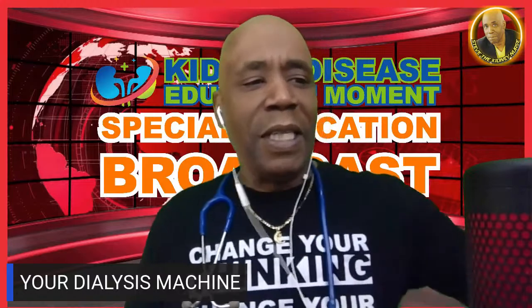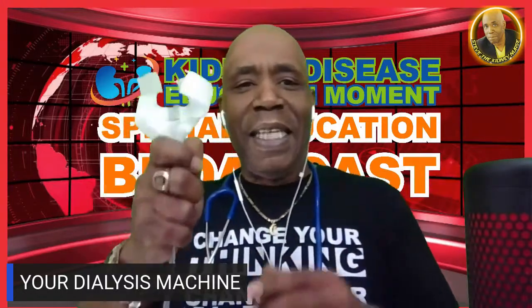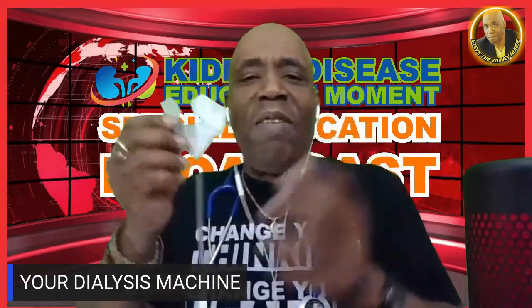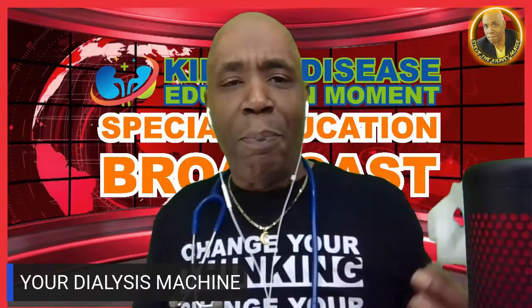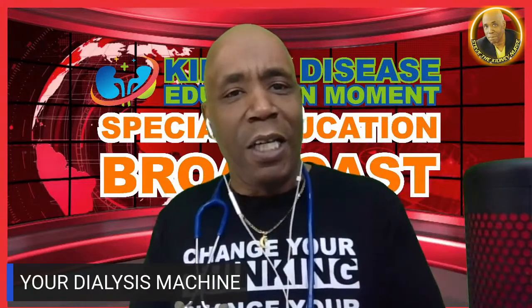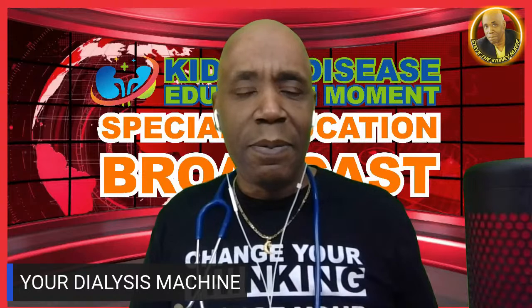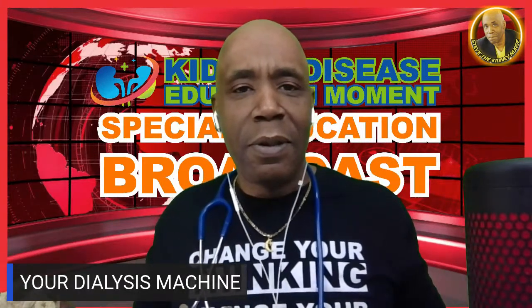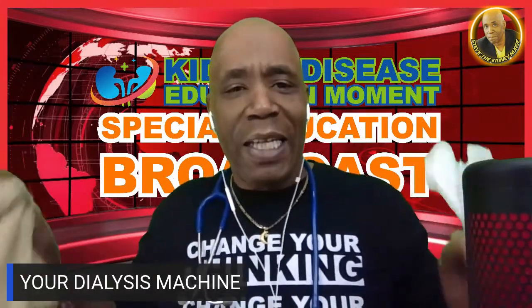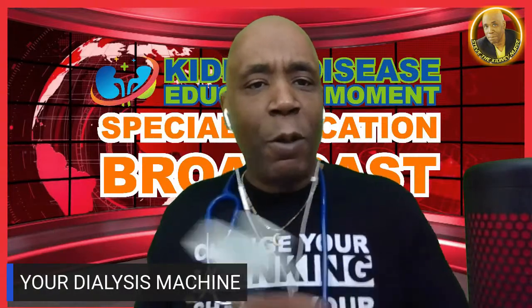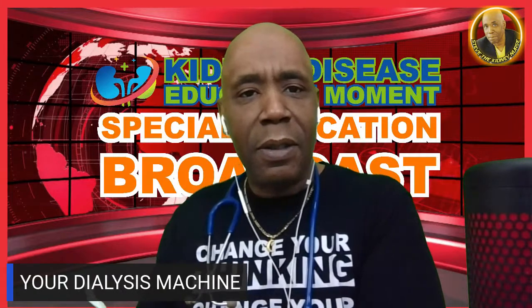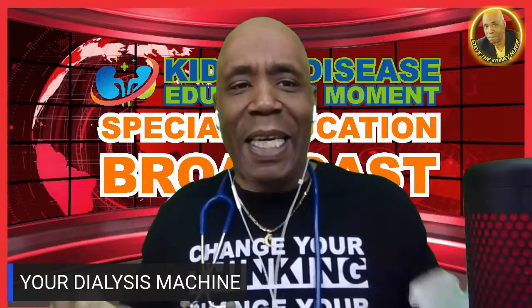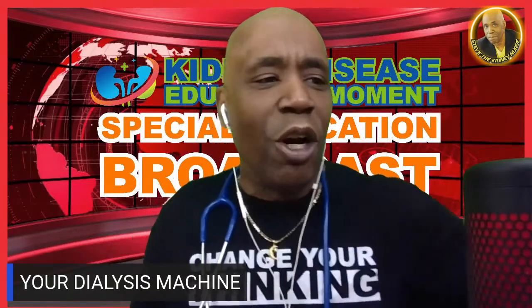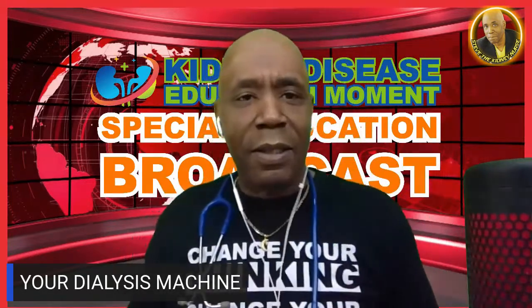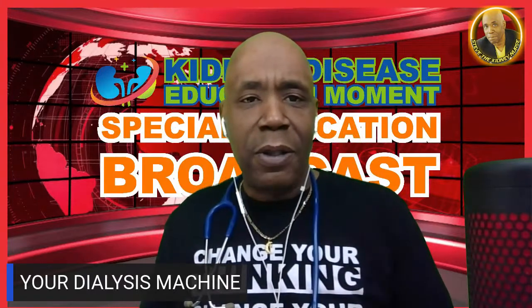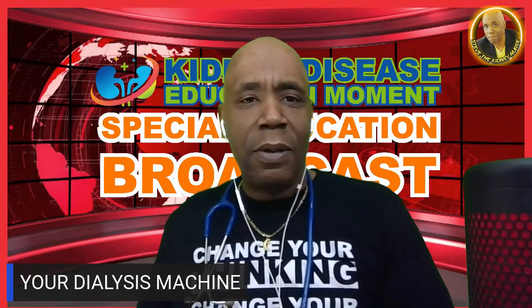So these are things you should know as a patient. What needle size are you on? Is it 15 gauge? Is it 16? Is it 17 gauge? Is it 14? What's my pump speed? Is it 300? Is it 350, 400? Is it 450? All this matters. It matters to how you feel, if you're getting the clearance taken out properly, your blood work at the end of the month. All of that, this waste getting cleared out of your body is a big deal, because that determines if you're itching, if you've got the metallic taste in your mouth, if you feel washed out, if you've got dry scalp.